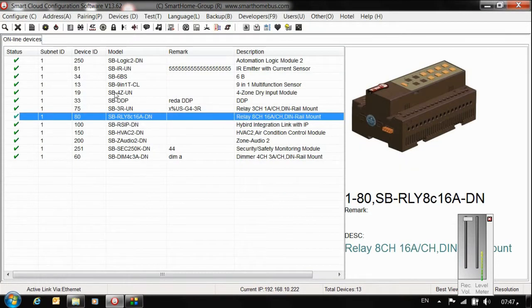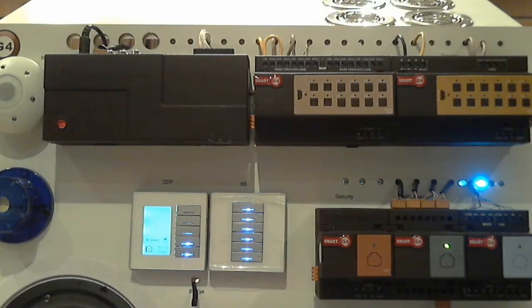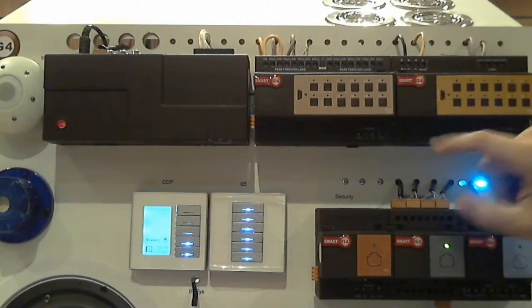It's very simple. Okay, now we have the third way which is called broadcast button. You have to go to the device itself. For example, I have here my dimmer and this is my relay. I want to change the dimmer. I want first to check my dimmer address. Press this broadcast button here - now the red color is coming. Go to the program, go to the Address menu, Broadcast Detection, press Detect Address. Now this is 60.